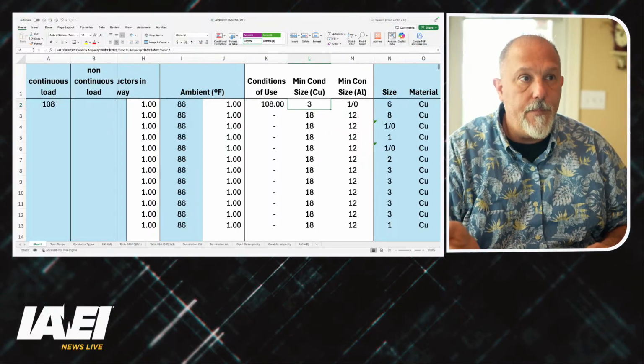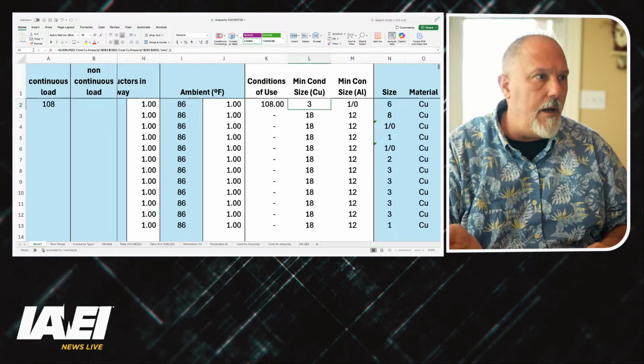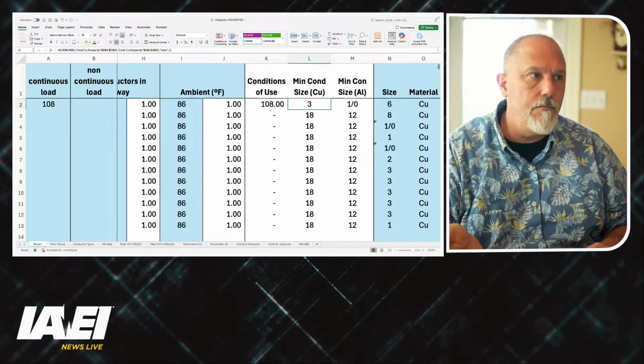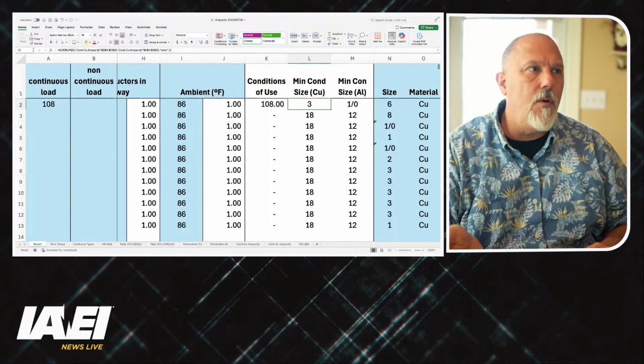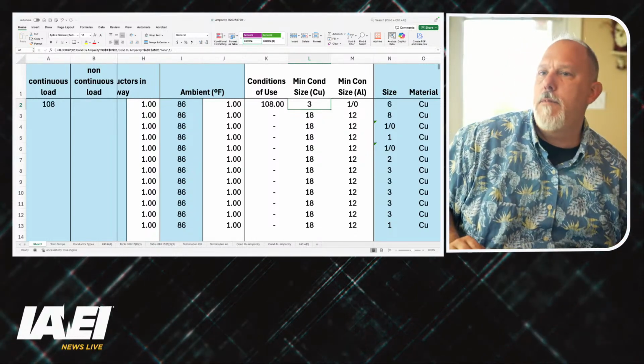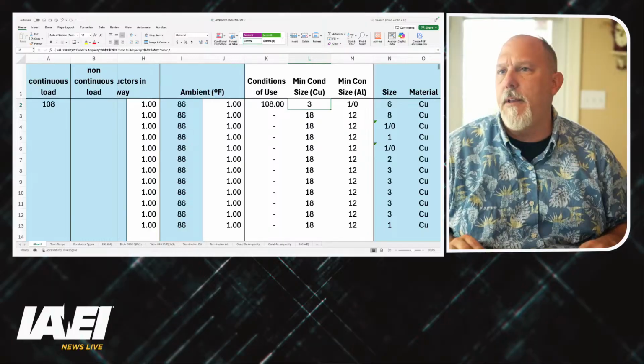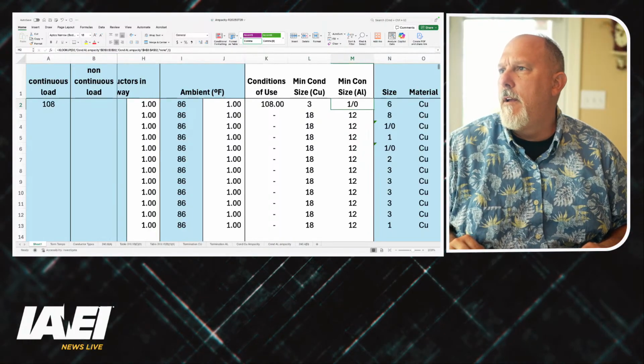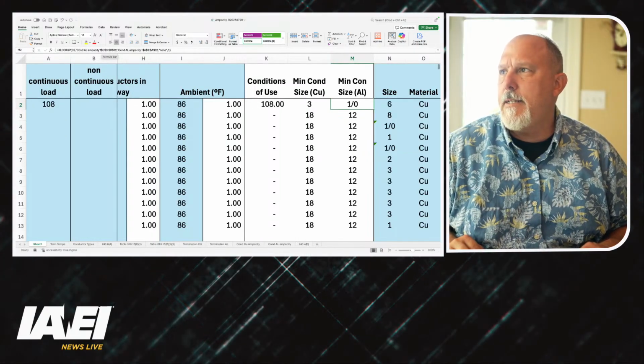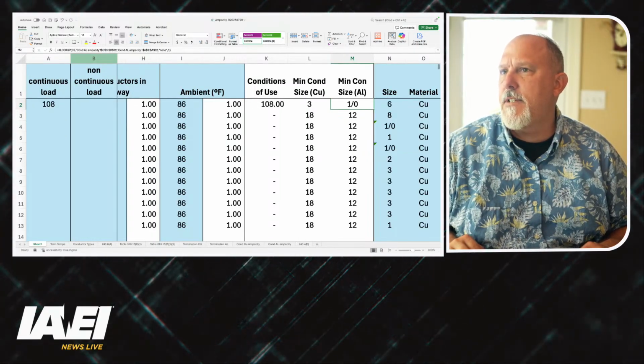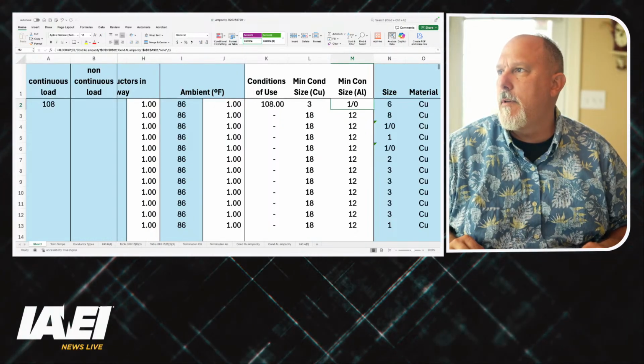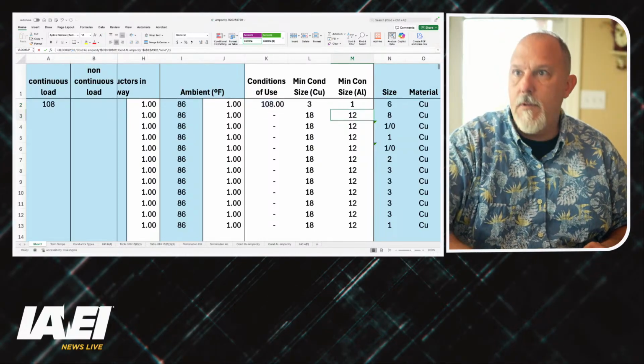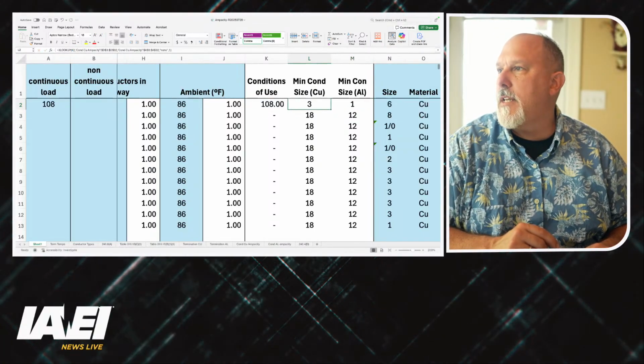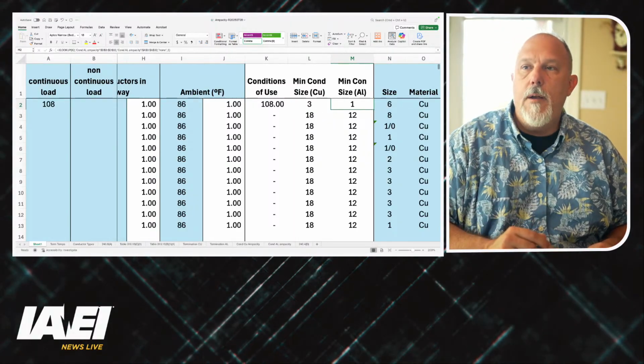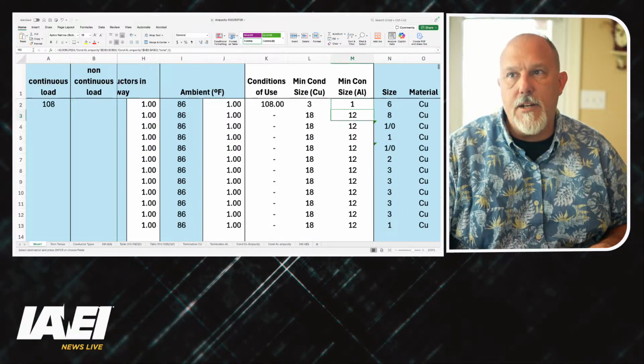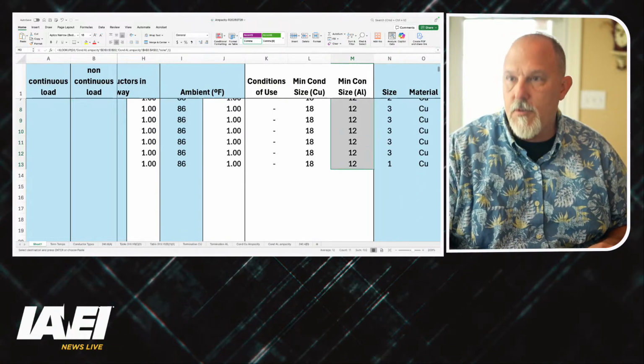For aluminum, I'm up to a 1. Why? I don't know why I have a 1 in here. I gotta check my D. For some reason, oh, I know why, K2. I gotta go to K2. So there's my 1. I want to make sure this is a K2, yep. So I have the wrong column. So my minimum size conductor, Control C, I need to copy this all the way down, Control V.